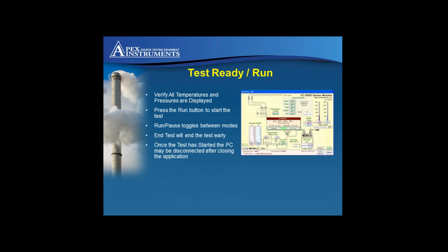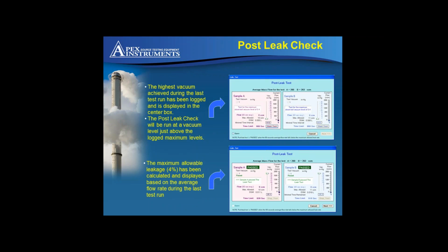The test run parameters and data available during the test can be viewed anywhere over the plant network. The test run data file is written to one of 99 memory slots, easily accessed, easily downloaded. At the end of the test run, there is another fully automated post-leak check. Once again, when it's completed, the test data file is updated, and this is a good time to download that file.